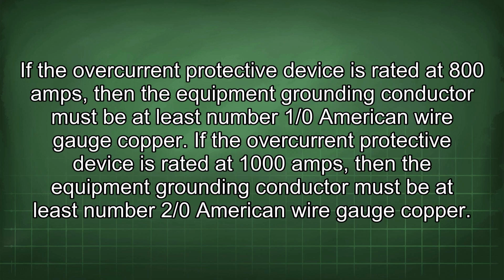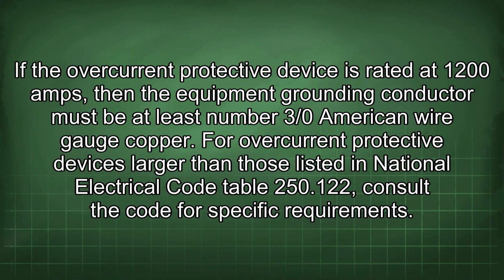If the overcurrent protective device is rated at 1000 amps, then the equipment grounding conductor must be at least number 2/0 American wire gauge copper. If the overcurrent protective device is rated at 1200 amps, then the equipment grounding conductor must be at least number 3/0 American wire gauge copper. For overcurrent protective devices larger than those listed in National Electrical Code Table 250.122, consult the code for specific requirements.